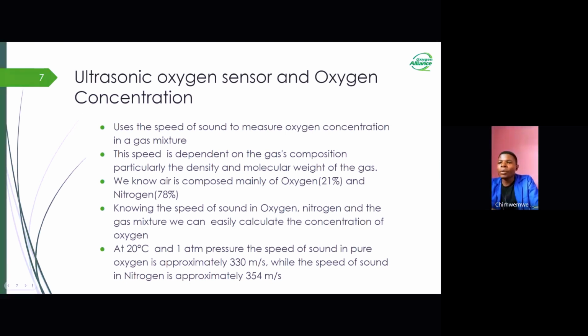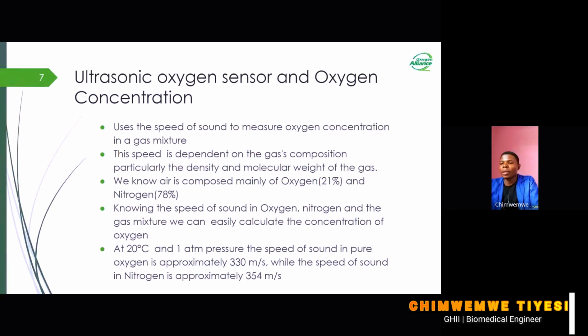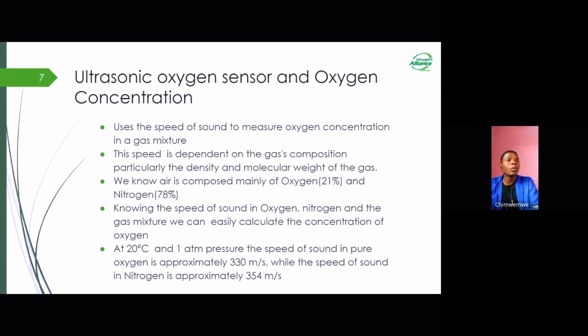The ultrasonic oxygen sensing is based mainly on the relationship between the speed of sound in a gas and its molecular weight. This principle is particularly useful for measuring the concentration of two gases in a mixture, like oxygen and nitrogen. We all know that air is composed mainly of oxygen, which is 21%, and nitrogen, which is about 78%. At 20 degrees Celsius and 1 atm pressure, the speed of sound in pure oxygen is approximately 330 meters per second, while the speed of sound in nitrogen is approximately 354 meters per second. When we know the molecular weights of these gases, we can determine the volume percentages of each gas in the mixture by analyzing the speed of sound in the mixture.